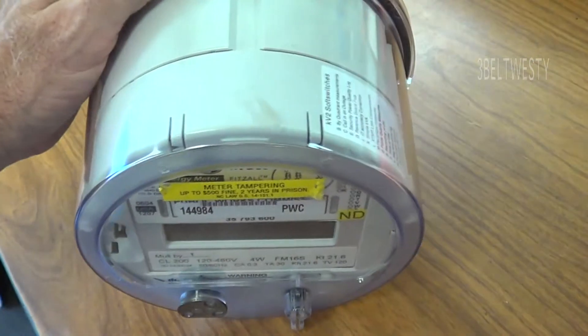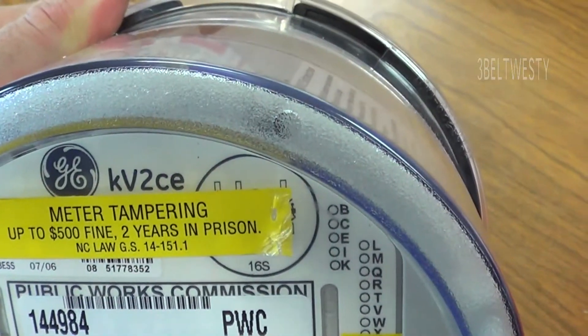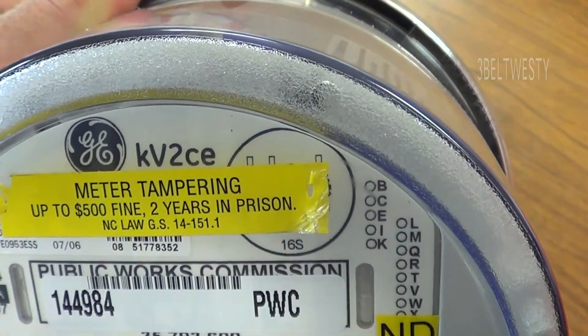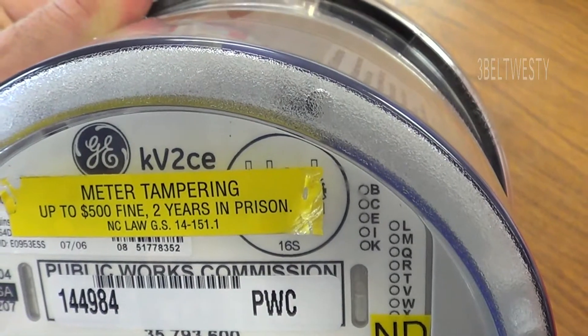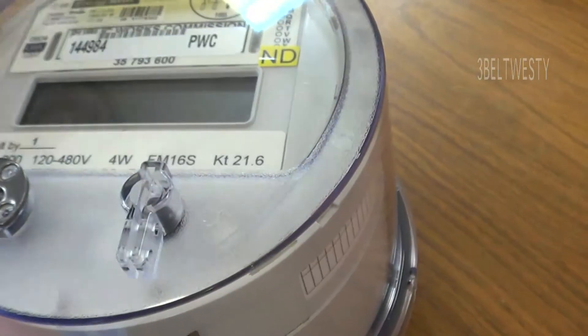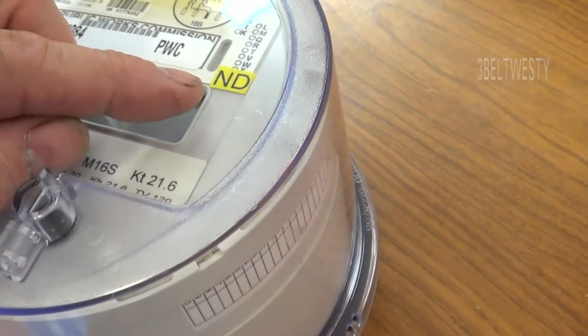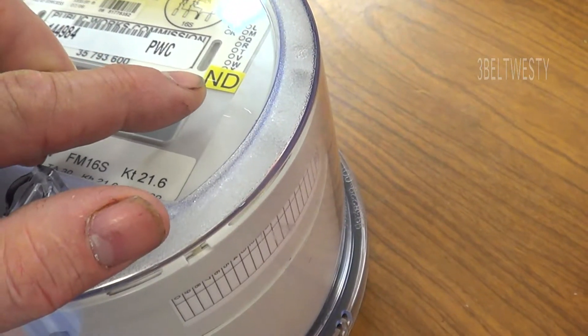Now what's interesting about this, this is a GE FitzAll KV2CE and the E on there has no demand feature and the electric company here is put on here ND for no demand.